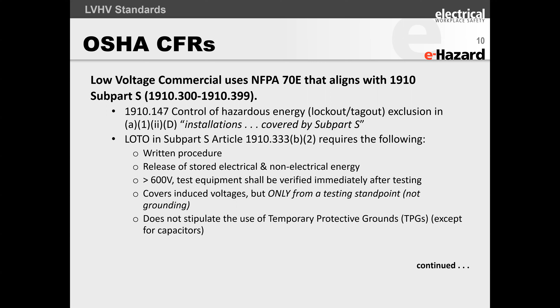Folks, all of you are familiar with this, so I'll go through it quicker. 600 volt test equipment and higher shall be verified immediately after testing. Almost all of us perform an instrument test both before and after testing the system. So it covers induced voltages, but only from a testing standpoint. It does not tell you how to work on these voltages, or how to work safely around induced voltages, and it does not stipulate the use of temporary protective grounds—those grounds we hang on high voltage systems—except for capacitors.